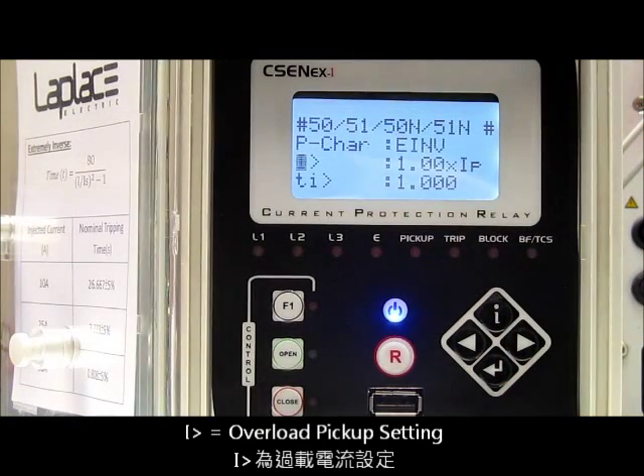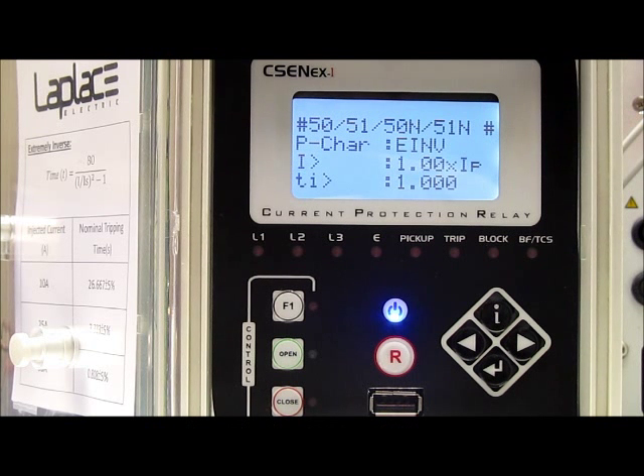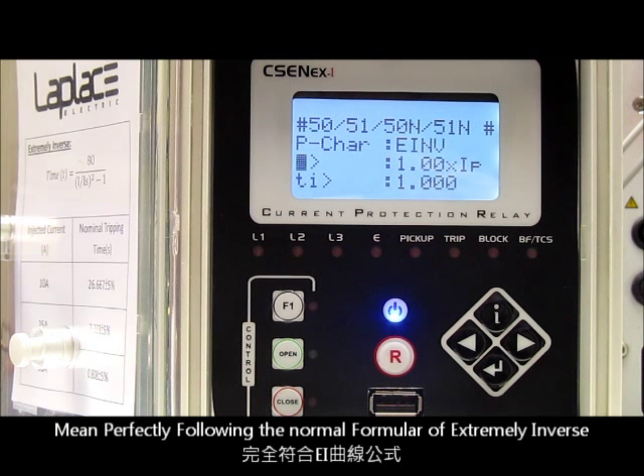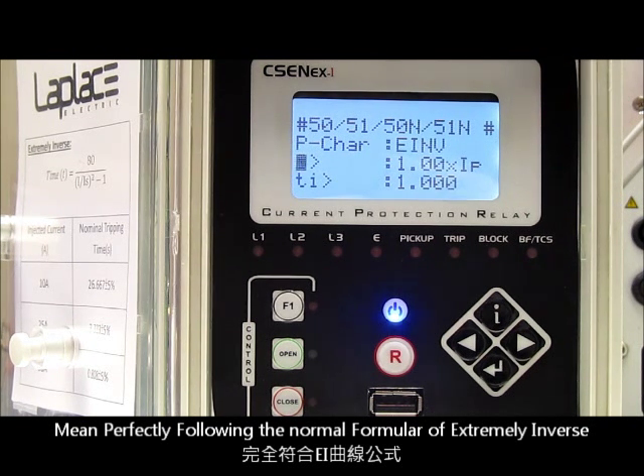I> means the overload pickup setting. For convenience, we set it to 1, which means 100%. This can perfectly follow the formula of extremely inverse.